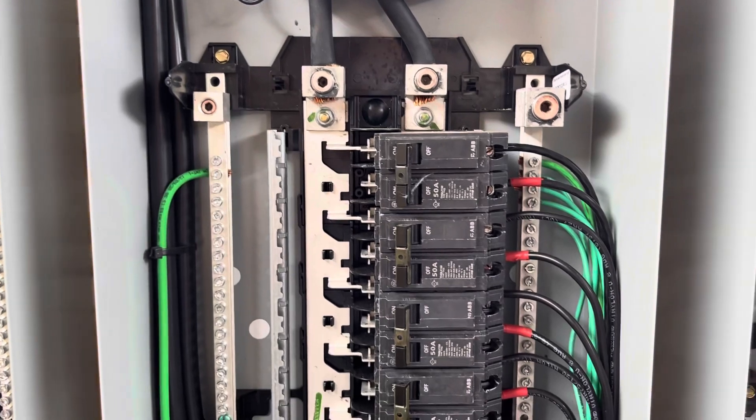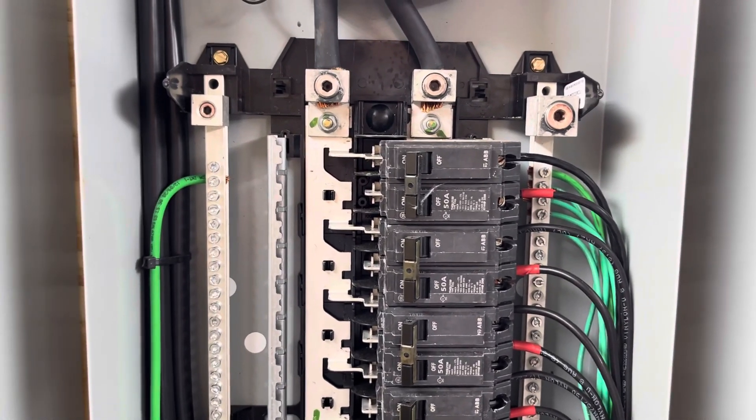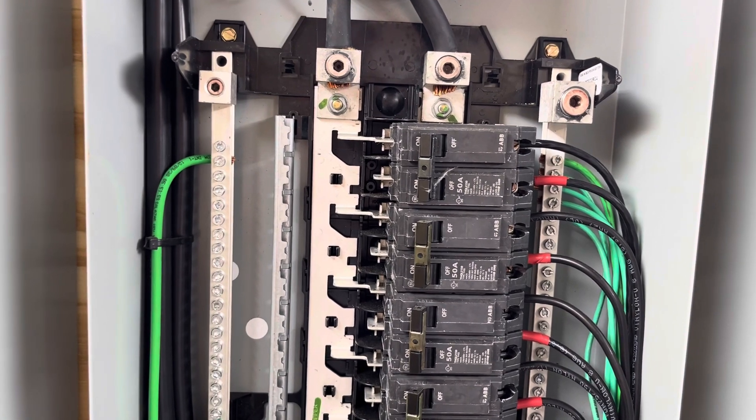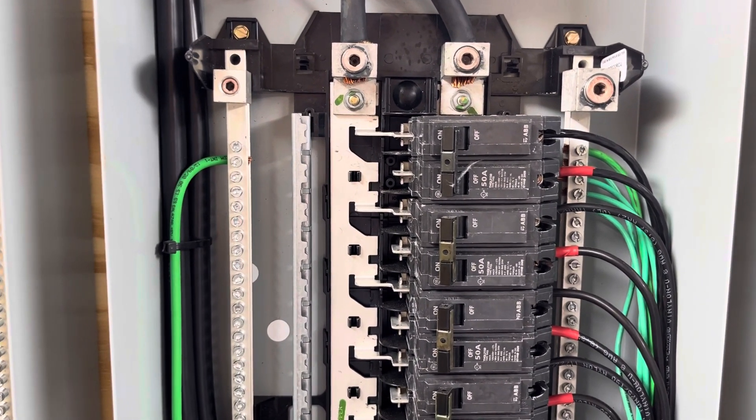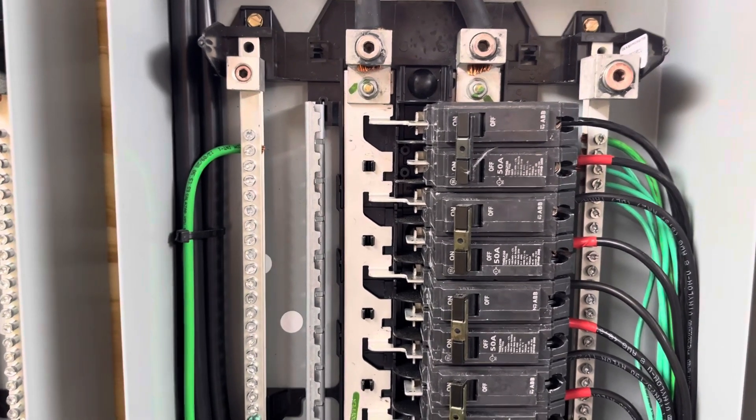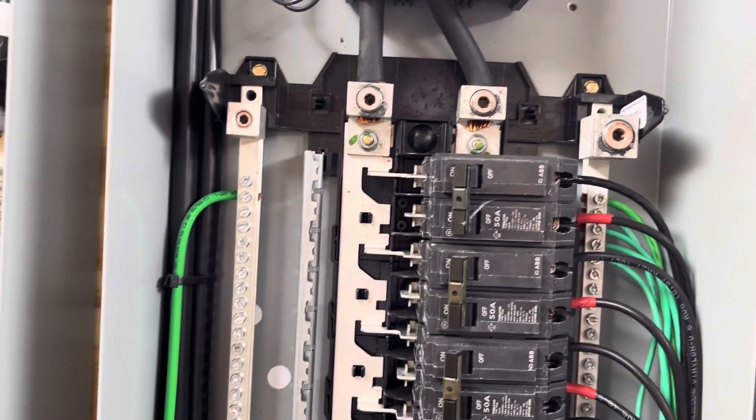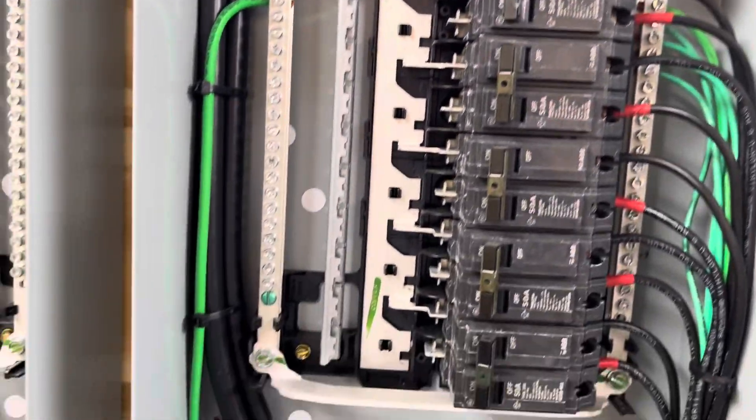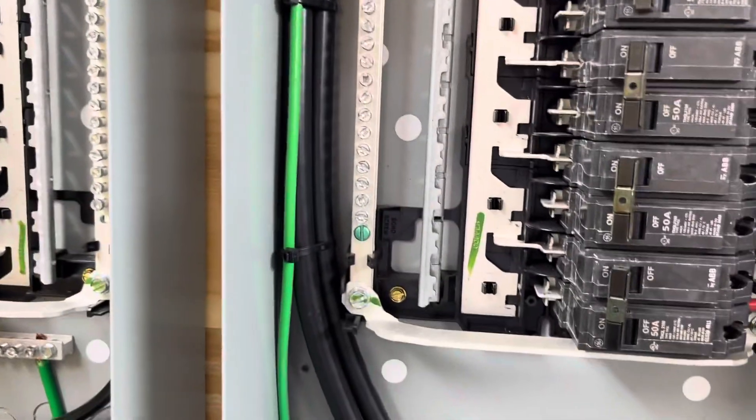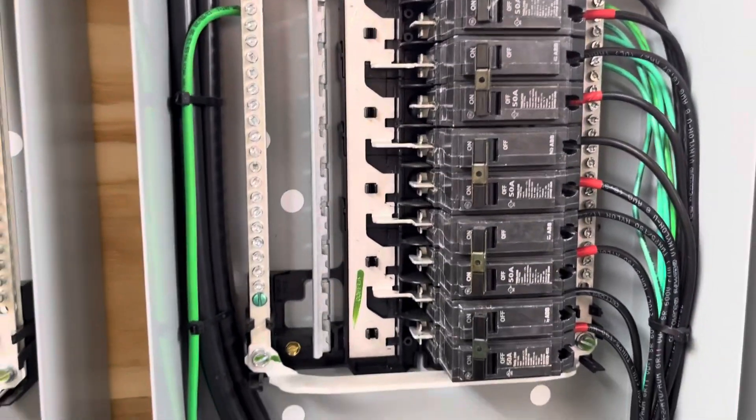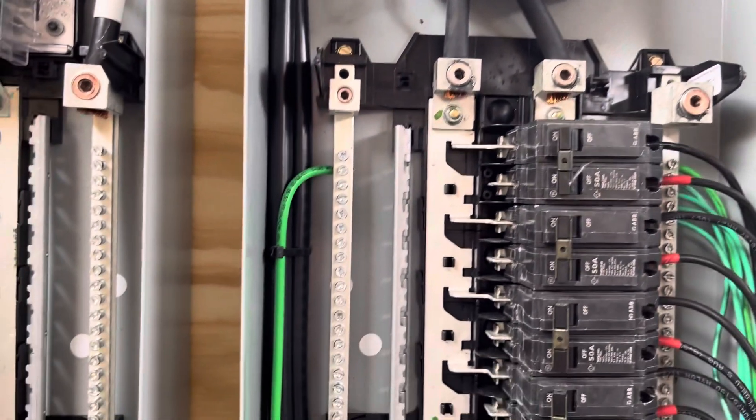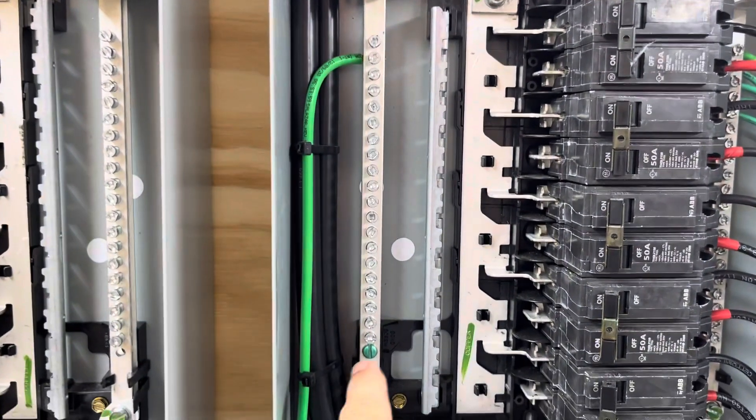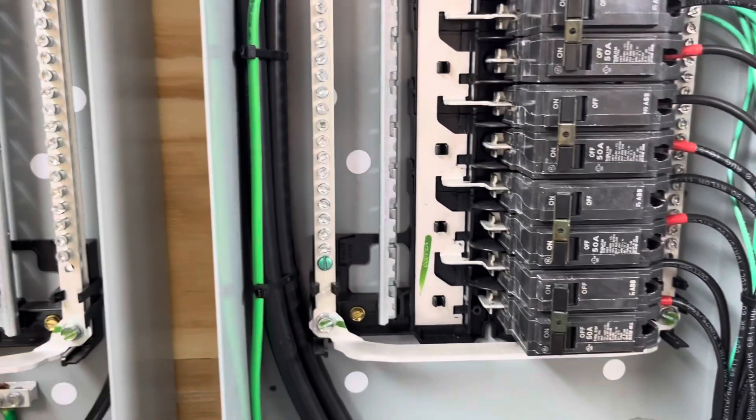Now, the inverter does not have a neutral connection. As I mentioned before, even though it's labeled N over there, it's actually L2 for the American market. So there's no neutral wire run from the inverter. Two hots and the ground. So I didn't have to worry about a ground bar because I didn't have a neutral to contend with. I've run all my grounds to this bar, and I've bonded this bar to the can.